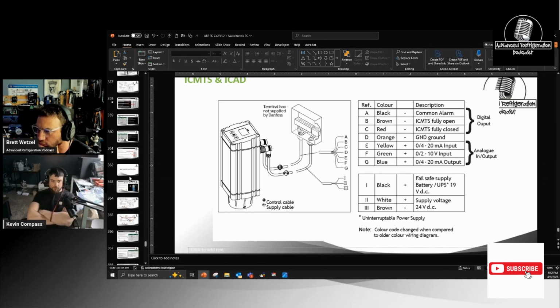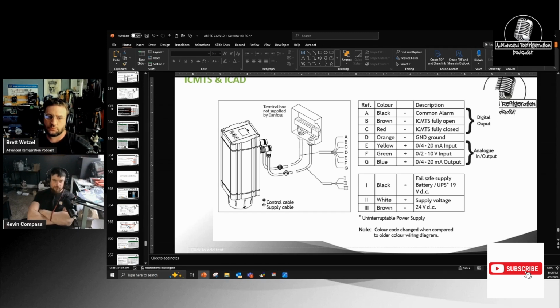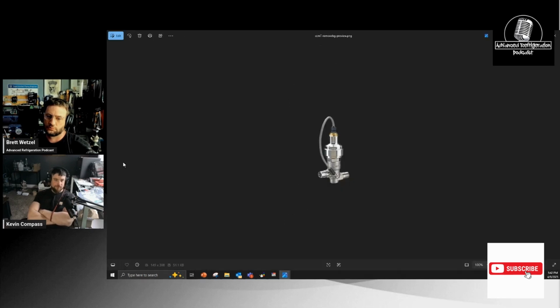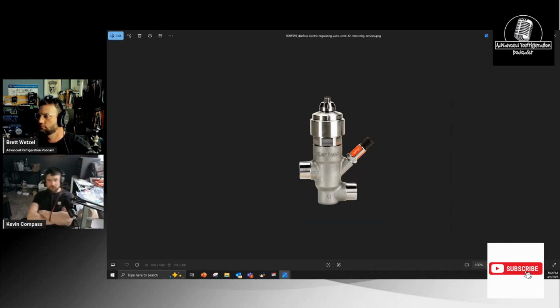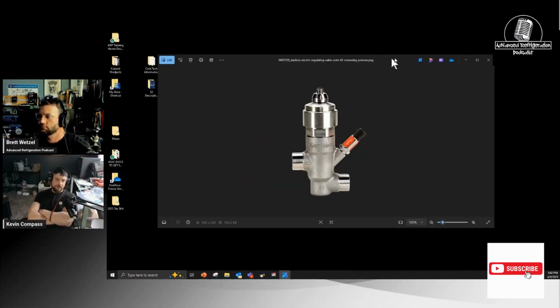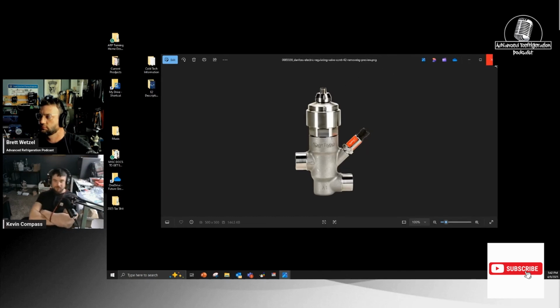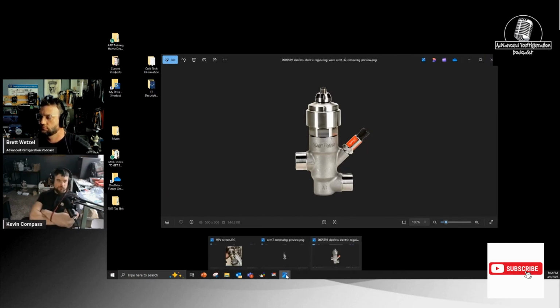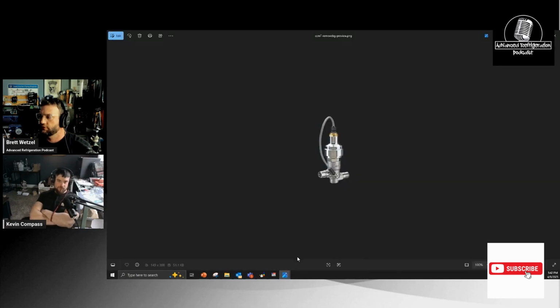It's a bipolar stepper motor. It has a screen in it, just like the one that Brett showed in that picture. It has a very fine screen in it, and it will plug up, and it has an O-ring on there. Now, the biggest problem I see on startup of these is they're wired wrong, and it becomes a mess. As Brett remembered from summertime, there was iPro wiring versus CCM wiring, two-valve controller versus CCM wiring, Danfoss controller versus CCM wiring, Carel versus CCM wiring. Every one of them is wired differently for the same valve.